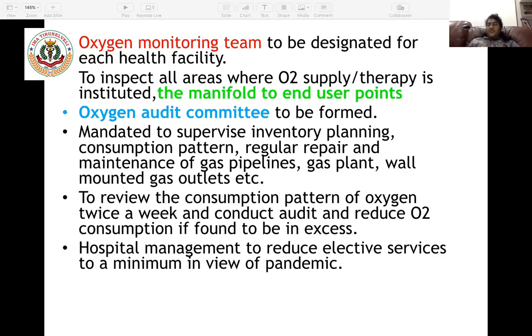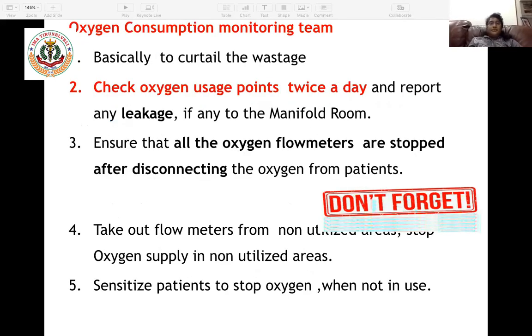We have to review the consumption pattern of oxygen twice a week in every hospital, conduct an audit, and reduce the oxygen consumption if found to be in excess. Hospital management should reduce elective services to a minimum in view of the pandemic. We set up a consumption monitoring team basically to curtail the wastage of oxygen. Check oxygen usage points twice a day, and that team has to report to the manifold if there is any leakage. Ensure that all the flow meters are stopped after disconnecting from the patients.